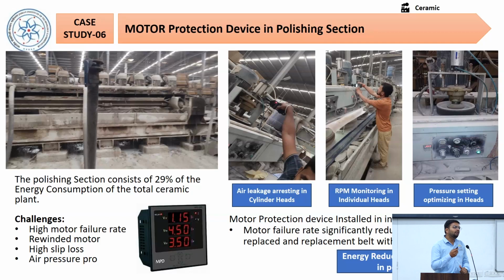So we now identified an application for a motor protection device. With the motor protection device, we can set the ampere, and after achieving that ampere, the motor can trip. So we identified that the failure is due to the operation. Operation error due to unskilled employees is also there, because local employees are used for the operation.